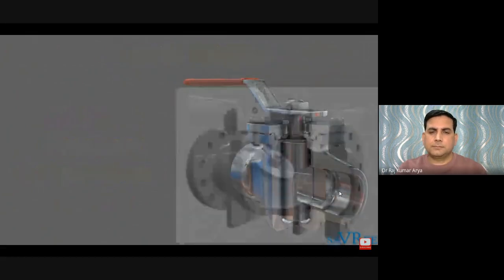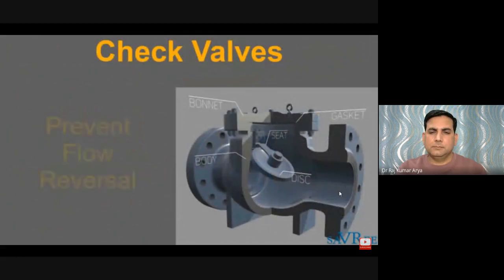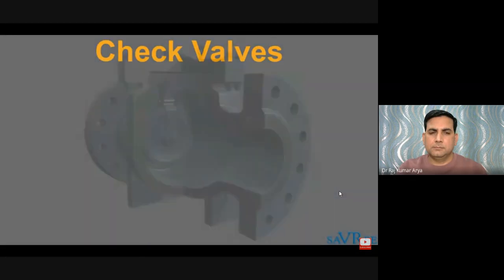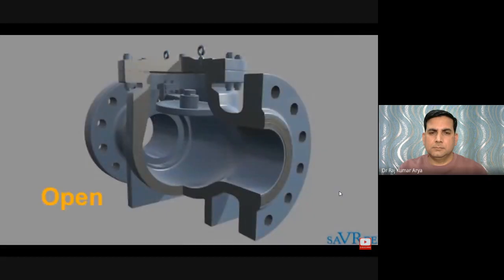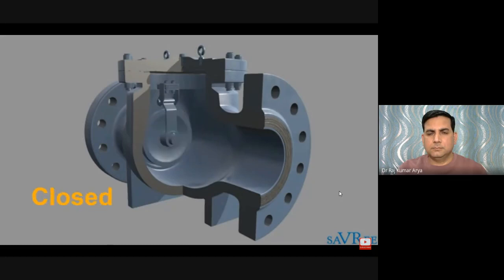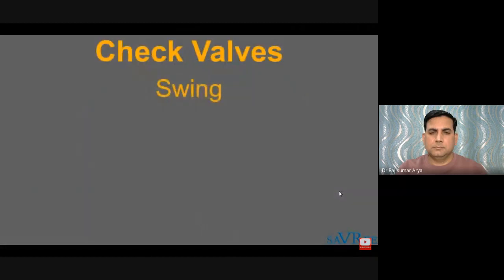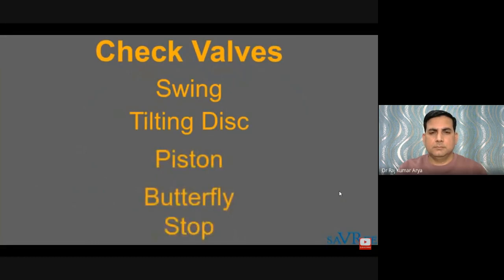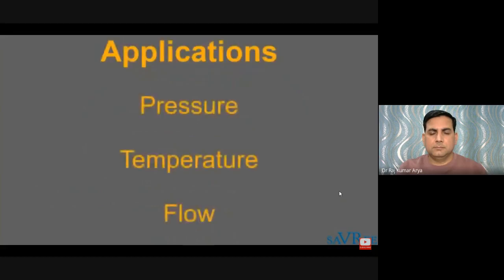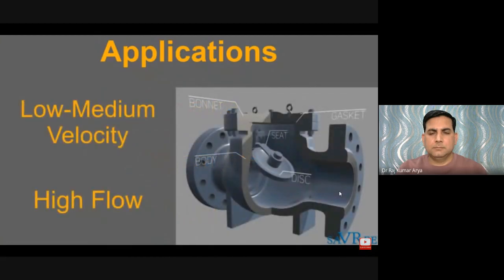Check valves are designed to prevent the reversal of flow in a piping system. They are activated by the flow of material in the pipeline: the pressure of the fluid opens the valve, while any reversal of flow closes it. Closure is accomplished by the weight of the check mechanism, back pressure, a spring, or any combination of these. The most common types are swing, tilting disc, piston, butterfly, and stop valves. The type used depends on system pressure, temperature, and flow requirements. Swing check valves are well suited for medium velocity, high volume flow applications with a relatively low pressure drop.